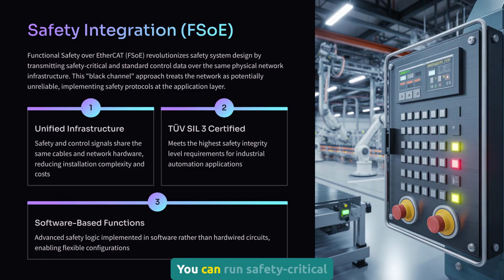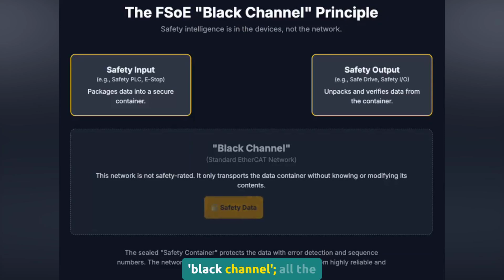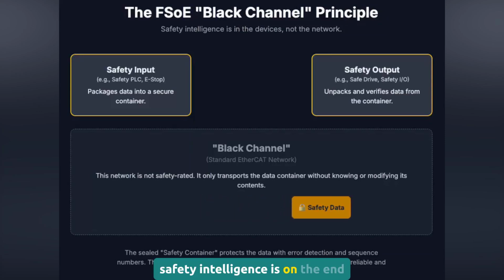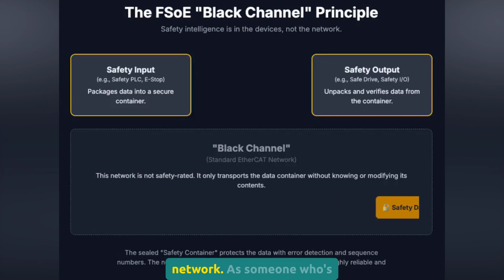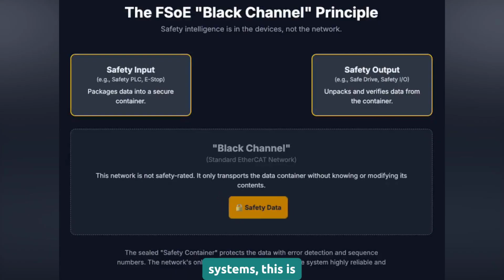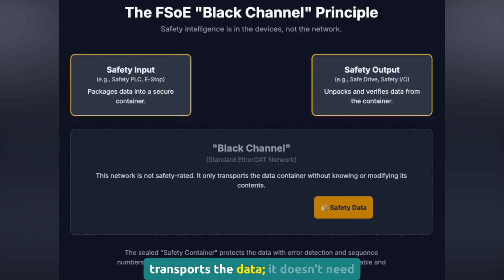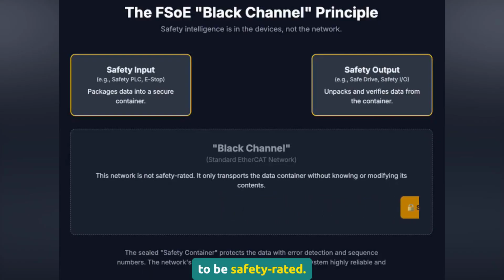After decades of installing separate safety systems with dedicated relays and hardwired circuits, Safety over EtherCAT also caught my attention. You can run safety-critical and standard control data on the same cable. The approach they use is called black channel. All the safety intelligence is on the end devices, not the network. As someone who's had to certify safety systems, this is brilliant. The network just transports the data. It doesn't need to be safety rated.